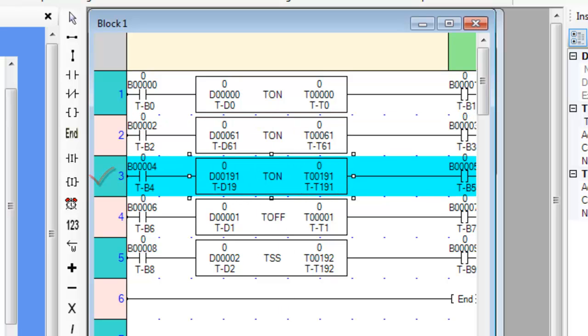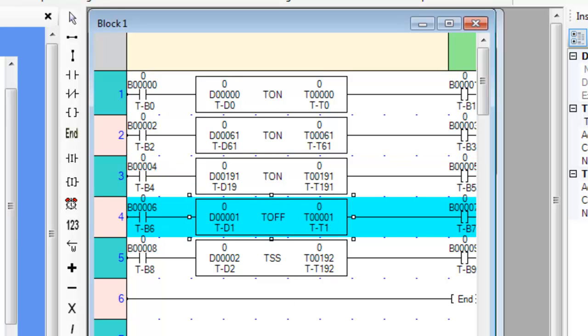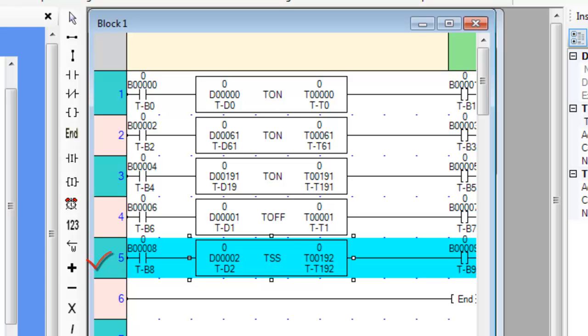Instead of using a constant value for the preset register, we have used internal data register D0. By doing this, we can adjust the amount of time the timer runs before it reaches the preset value and turns on the output coil. In this example, we use internal bit coil B0 to activate the timer and B1 as the output coil. On rung 4, you see an off timer. An off timer is very similar to an on timer except the input coil must be off to activate the timer, and the output coil will normally be on, shutting off only when the timer reaches the preset value. Since the address selected is T1, this is a 10 millisecond timer. On rung 5, we have a single shot timer using address T192 so that it will count in 1 second increments.